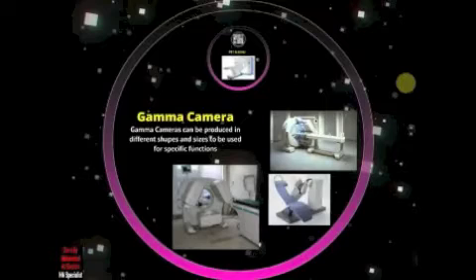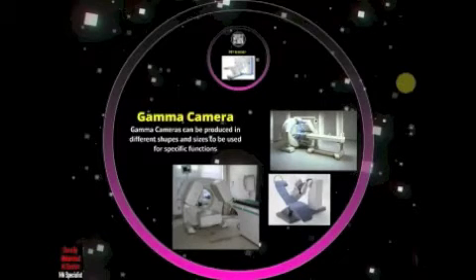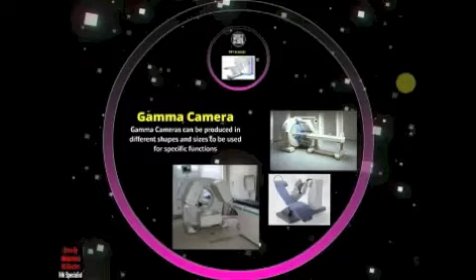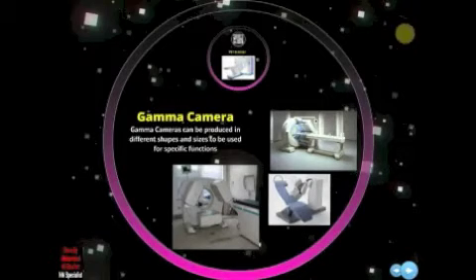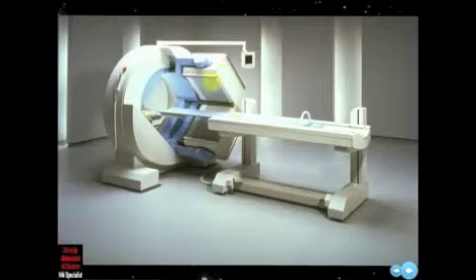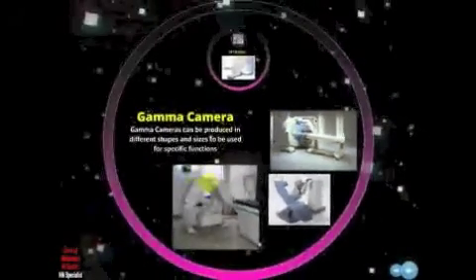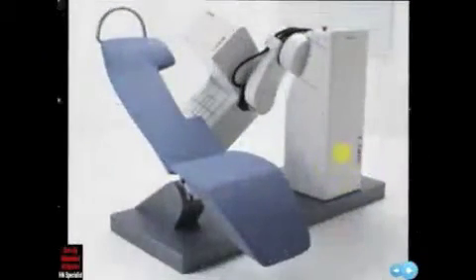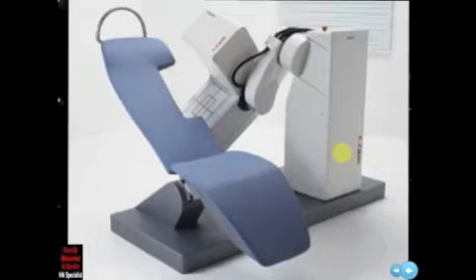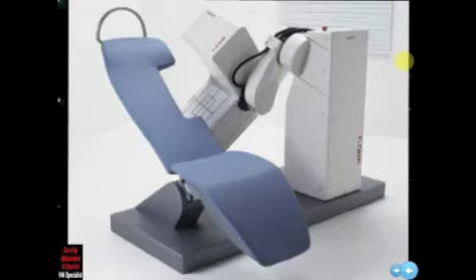This is the main device in our departments, known as the gamma camera. As I explained earlier, our imaging is based on gamma rays, so the name comes from this phenomenon. The most common device used is the dual-head gamma camera. It can come in several shapes and forms — triple head, or this one known as the C-cam, which is a dedicated cardiac camera. The benefit of this camera is that if a patient has a lumbar injury or is too obese to be seated, we can use this machine because it operates at a 45-degree angle rather than a supine position.